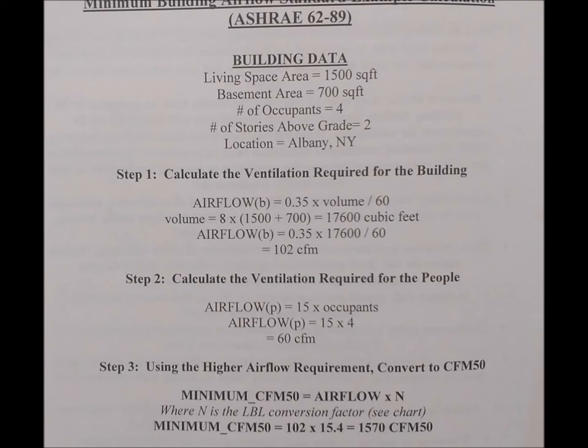Volume equals 8 times (1,500 plus 700) equals 17,600 cubic feet. Airflow equals 0.35 times 17,600 divided by 60 equals 102 CFM. Step 2: Calculate the ventilation required for the people. Airflow equals 15 times the number of occupants: 15 times 4 equals 60 CFM.